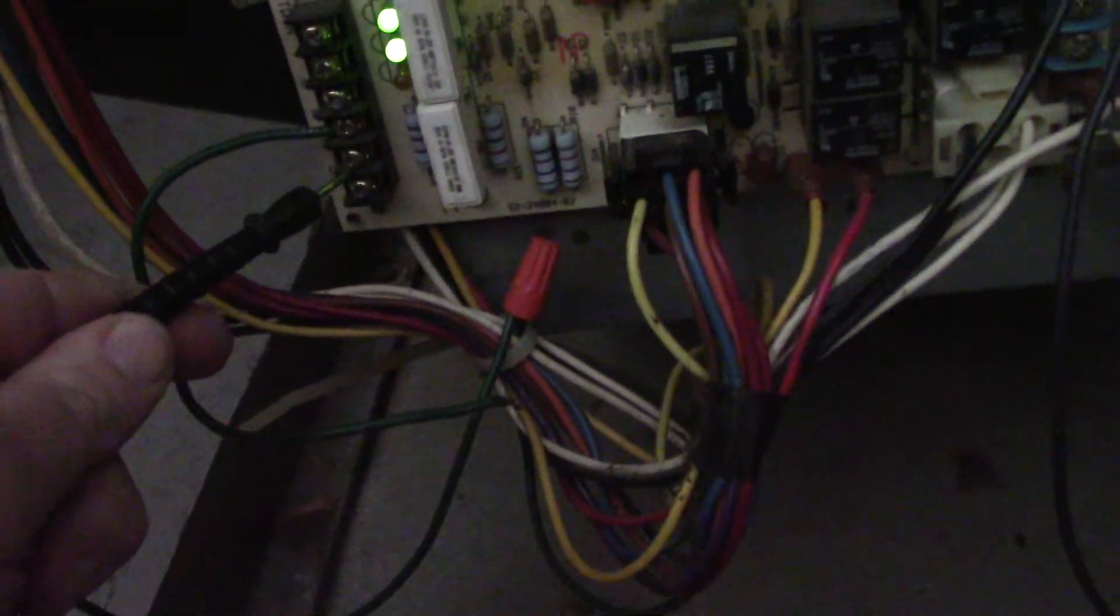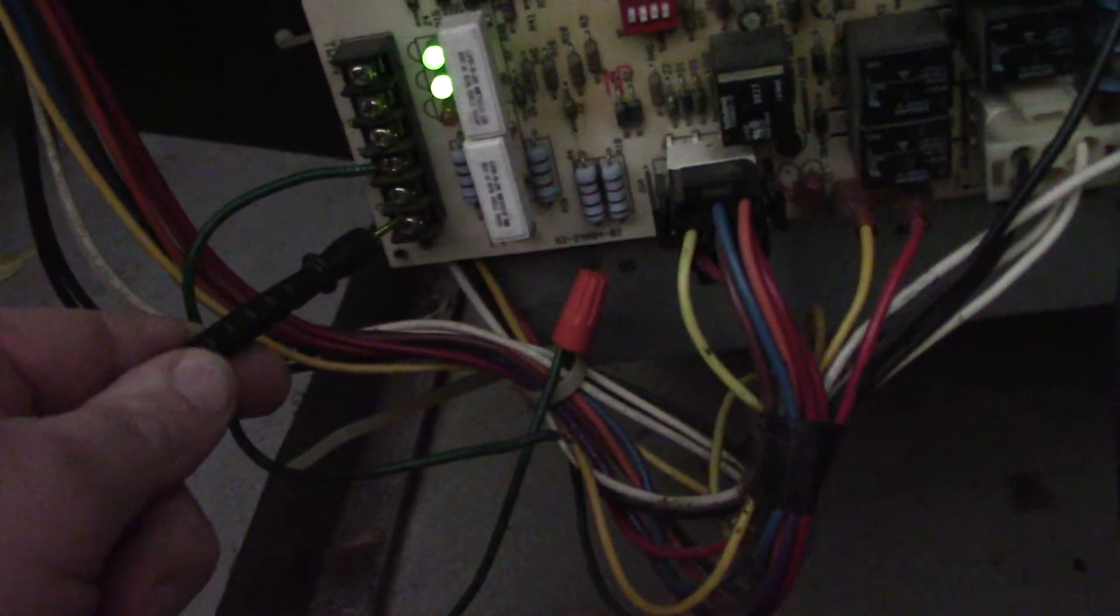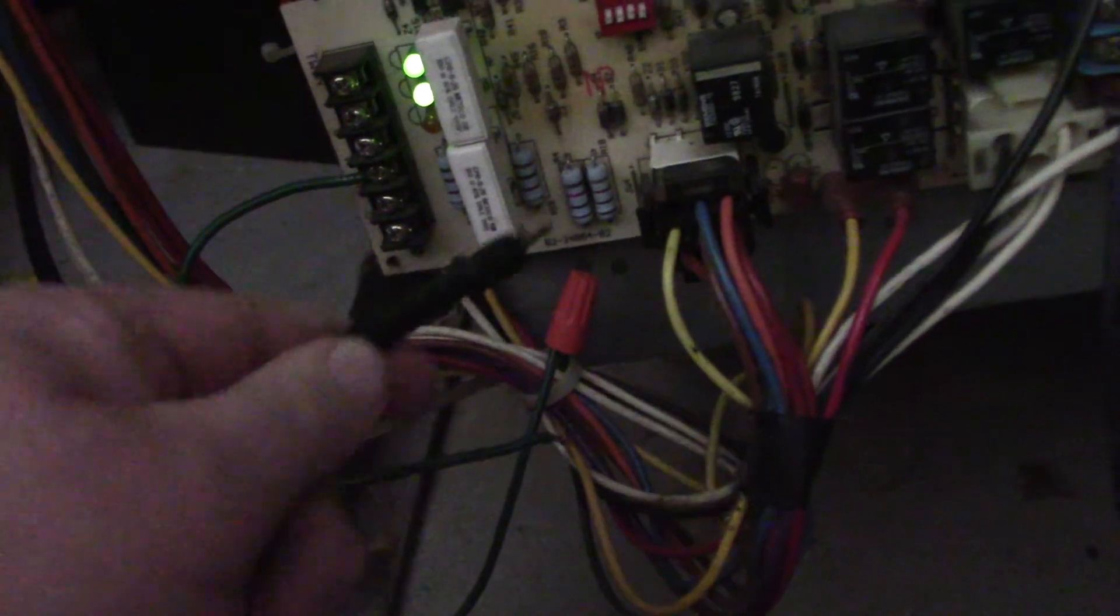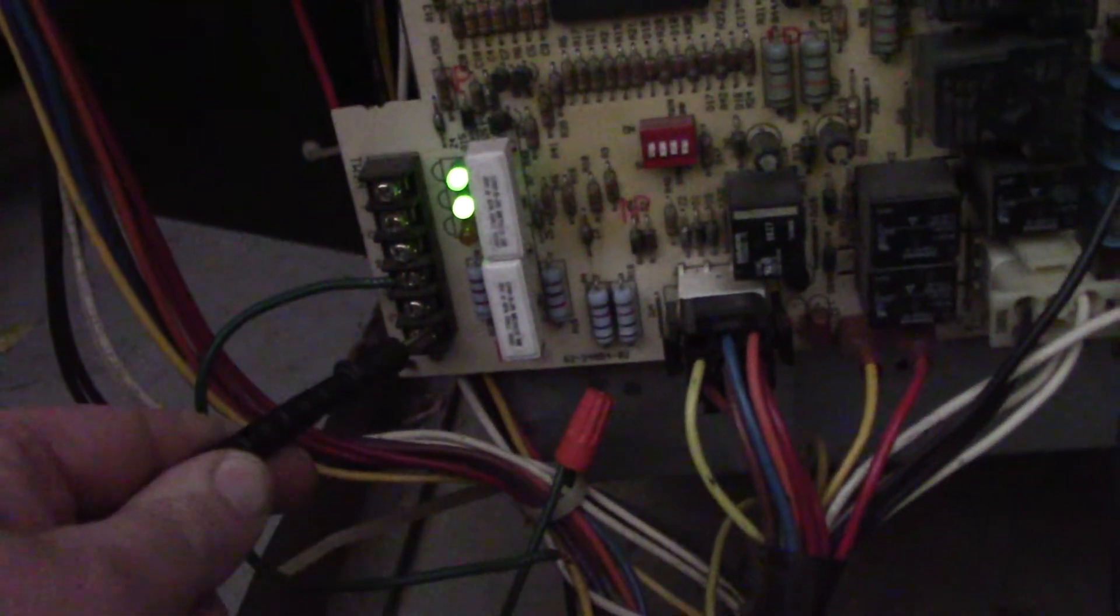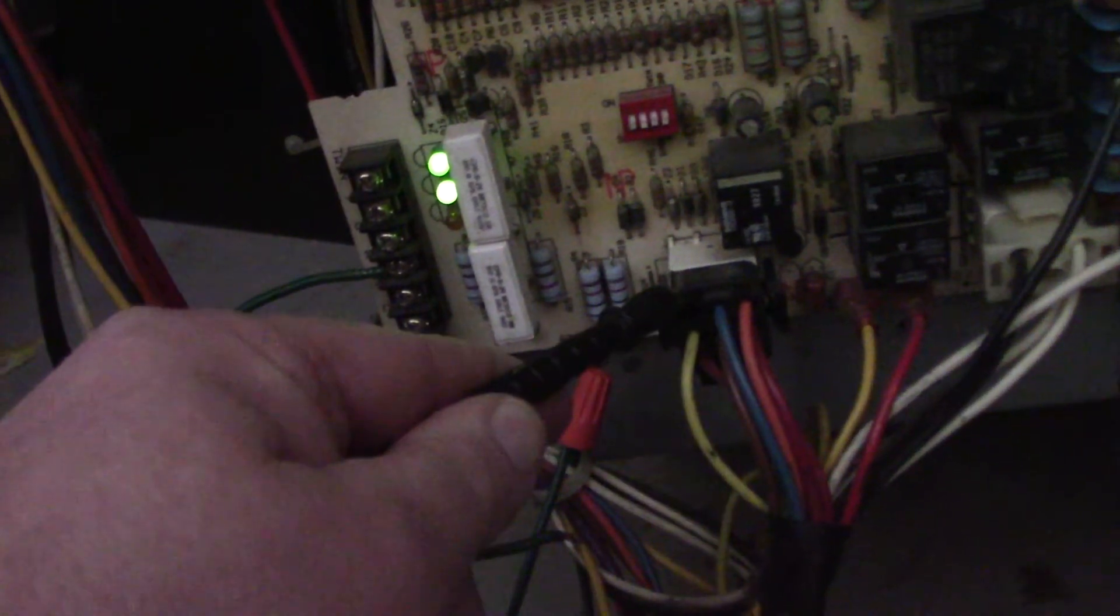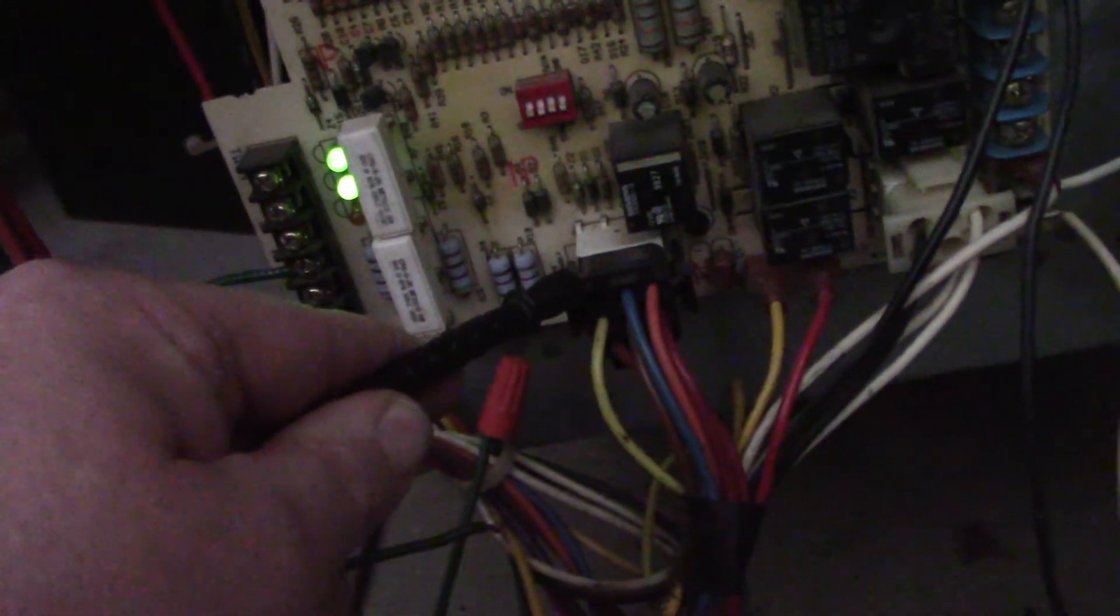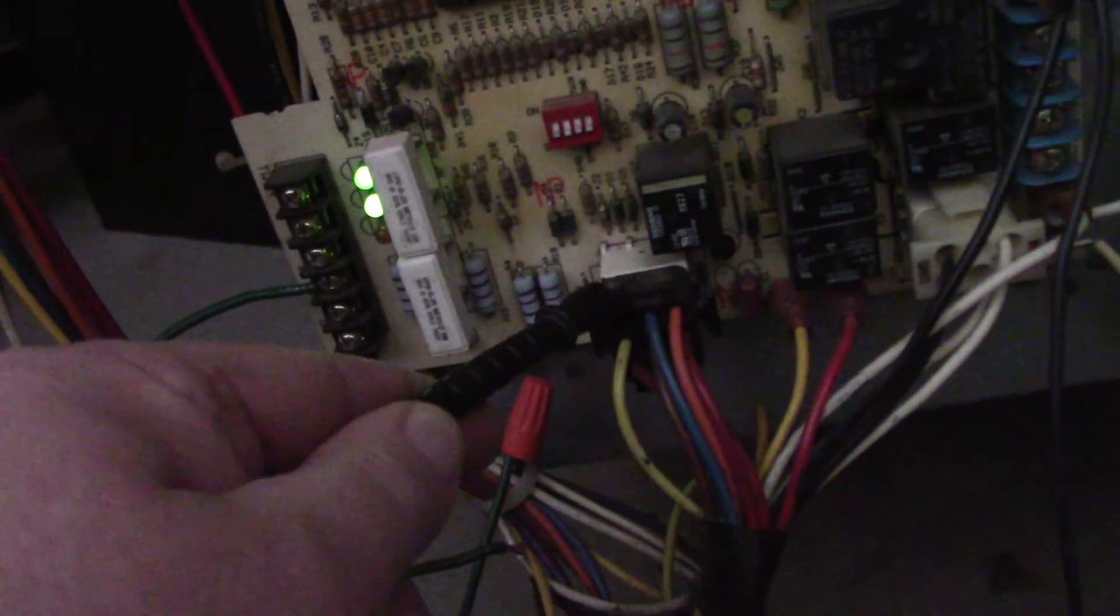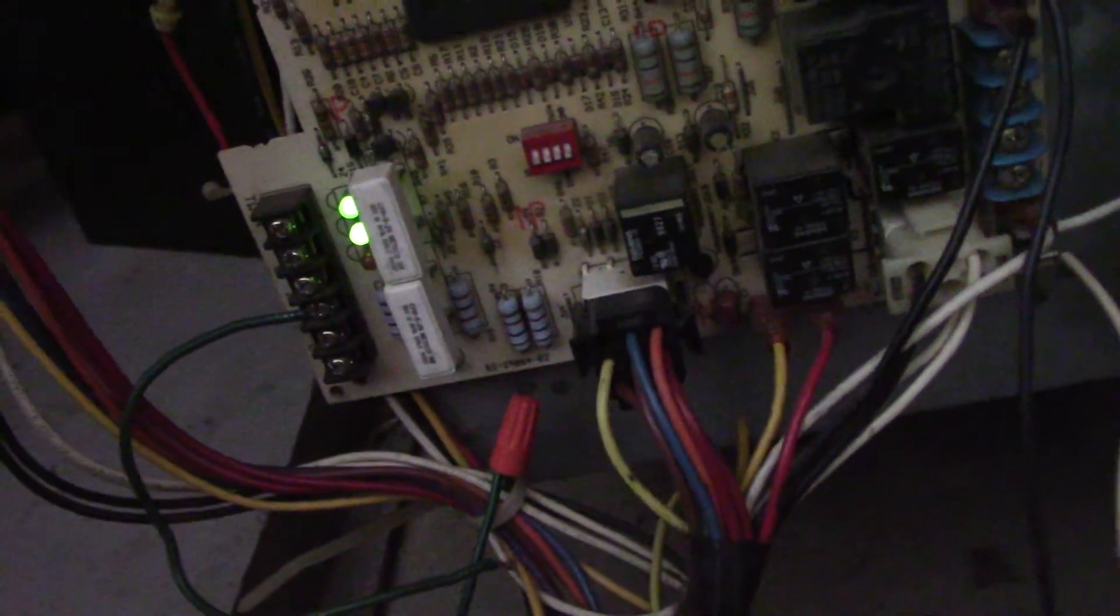You can also check too, like remember in another video I said the R and C, cause this right here connects electrically through that board to this plug right here. So if you have 24 here, you're more likely to have 24 here and 24 there. But if you don't have it here, you have to check here to differentiate between is it board or is it the transformer type of deal.